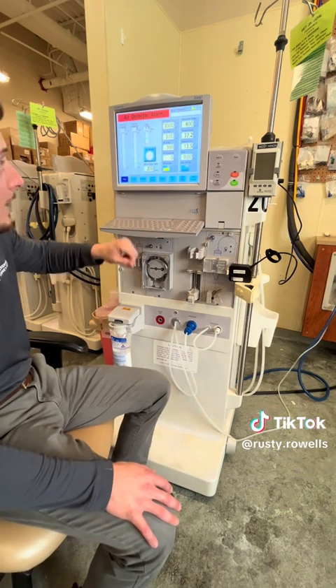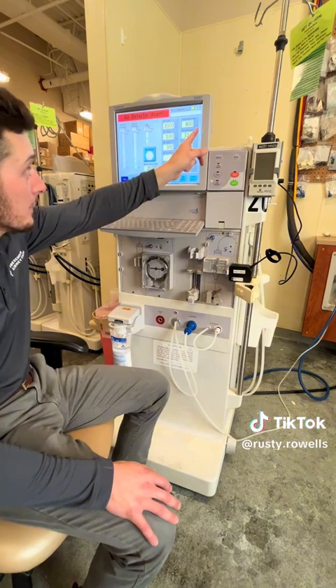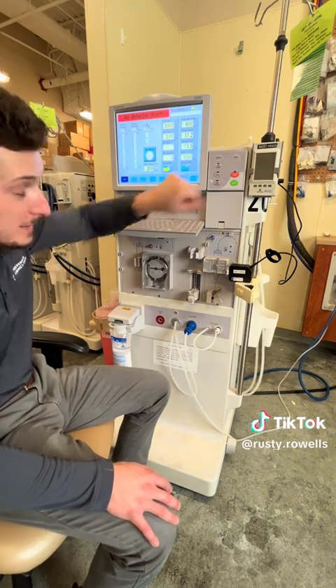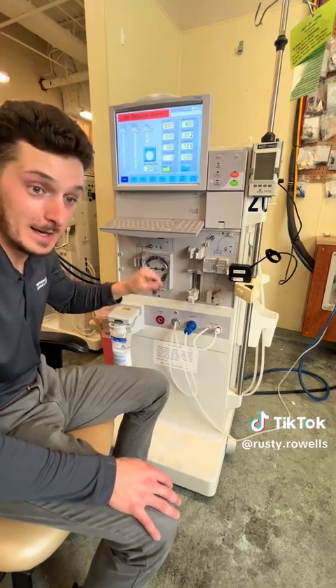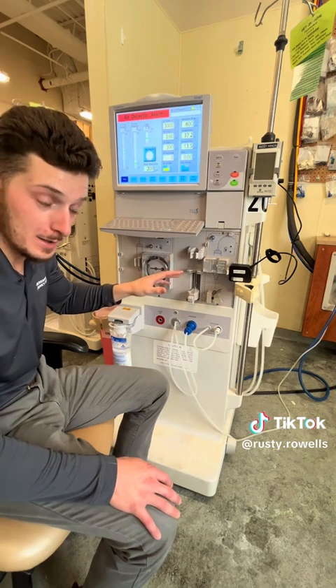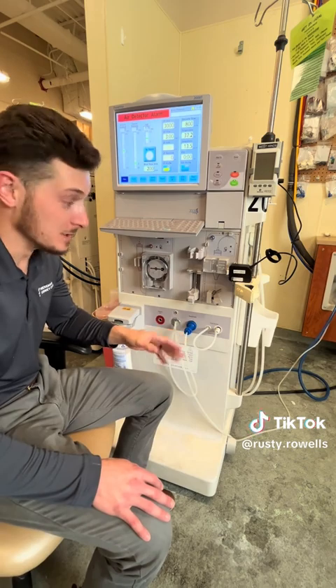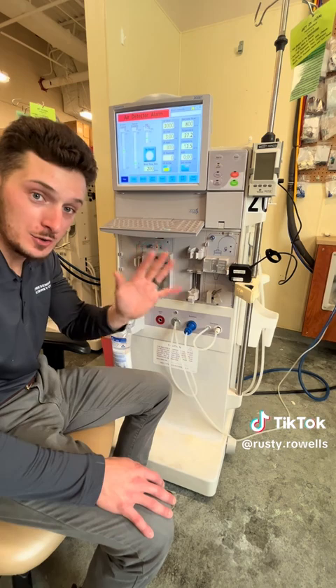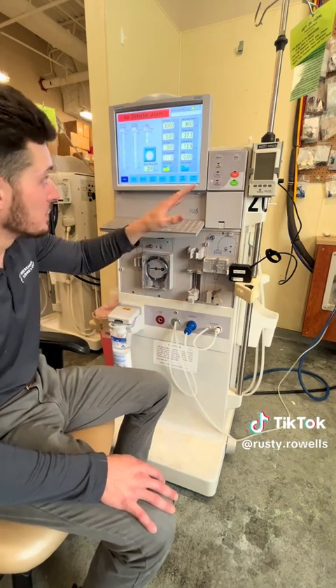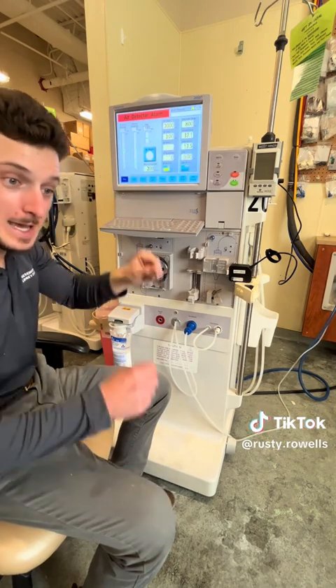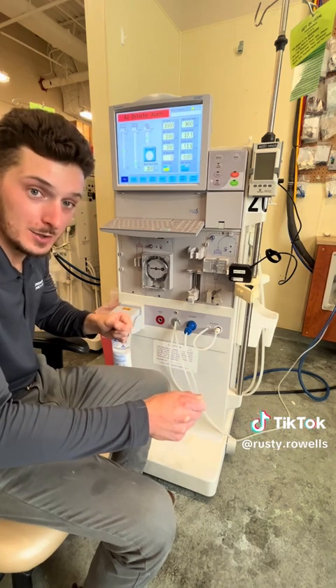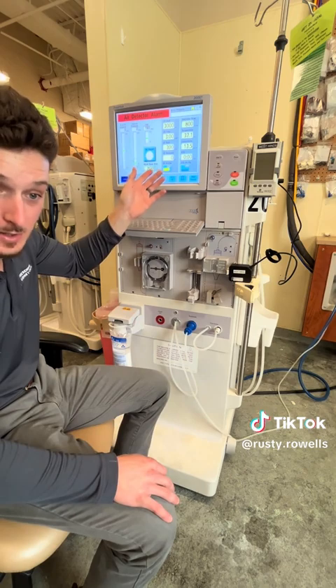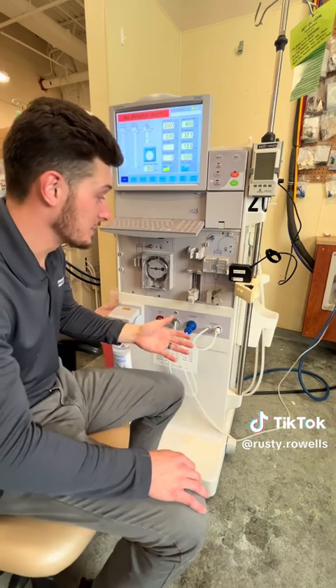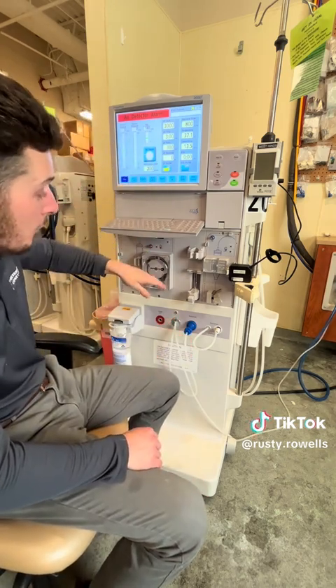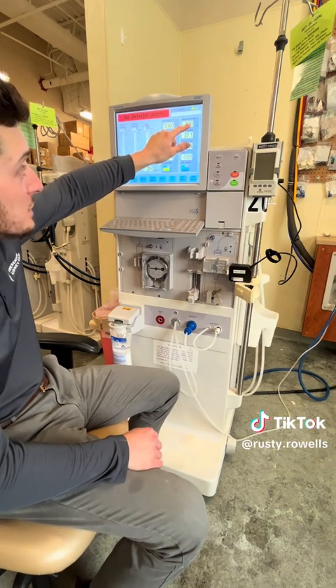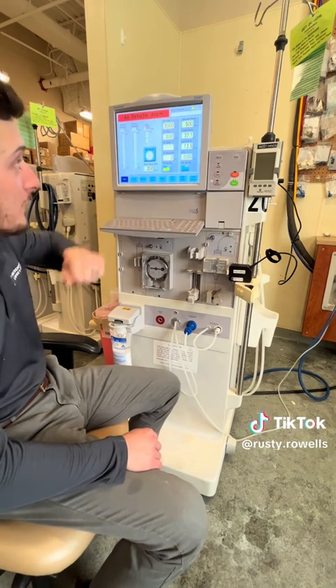So right now we're in dialysis and we have an 800 flow rate up here in the top right corner. Now if we were to cut this machine off, go straight into service mode and calibrate, we're going to get an operator error. Reason being, during that calibration, it wants to calibrate at a 500 flow rate. But for some reason, when you cut the machine off while it was running at an 800, it locks in that 800 flow rate during the calibration, and that's what is giving us the operator error. So what you have to do is turn the machine on, bring it up in dialysis, and change that from 800 to 500.